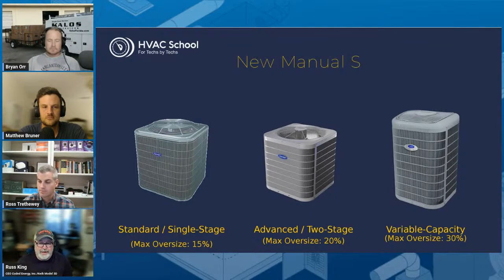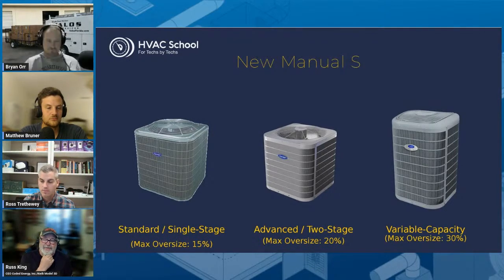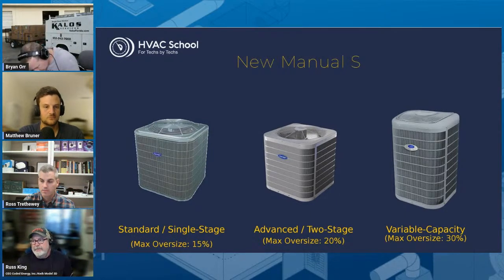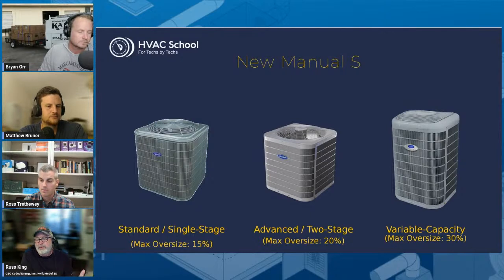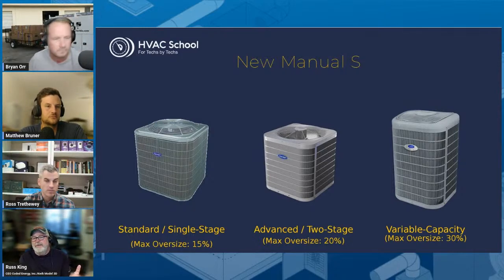Yeah, there's actually like 9 different options for sizing heat pumps. You've got the 3 main ones up there, but there's a lot of nuances now in the new Manual S, and in a lot of ways it's a lot more flexible. But with flexibility comes complexity, and it's not as simple as the old Manual S. There are 2 schools of thought to sizing a heat pump. You size the heat pump to the cooling load, and then if there's not enough heat, you make up the difference with strips. That's the old way to do it, right?